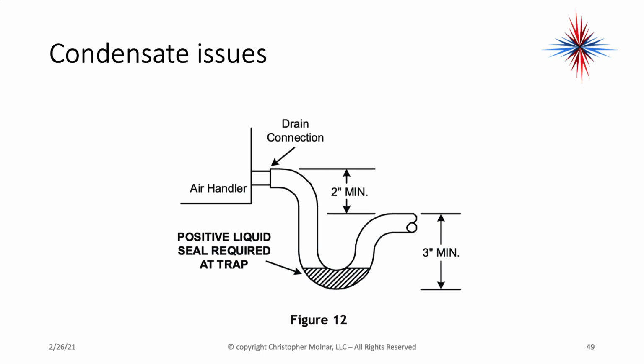Okay, so this is a condensate trap that is installed properly. You have a 2-inch minimum drop between the top of the trap and the air handler. Okay, you have to have 2 inches. That's required. Then your trap has to have a 3-inch minimum dip. That's under the 2 inches. So I have to have clearance of 5 inches here. Think about that when you're doing air handler installations.